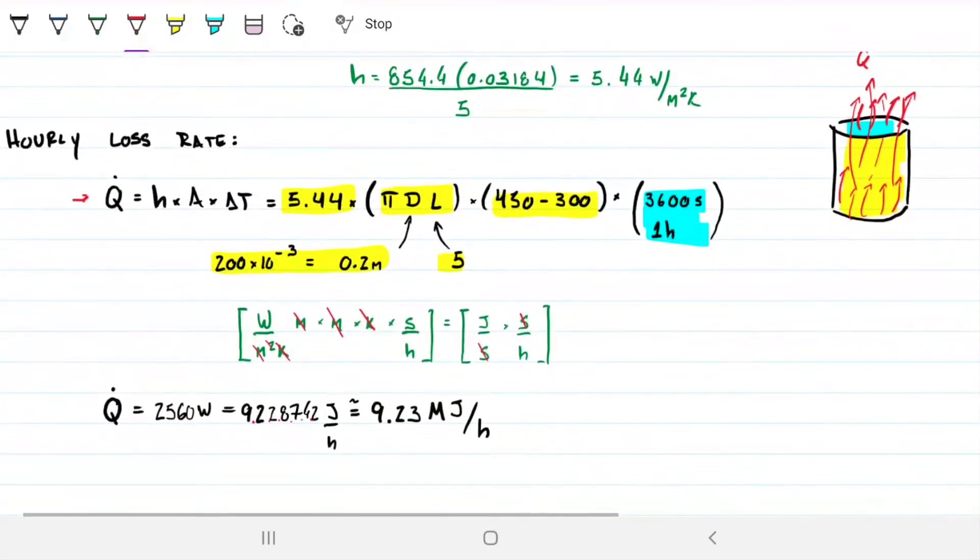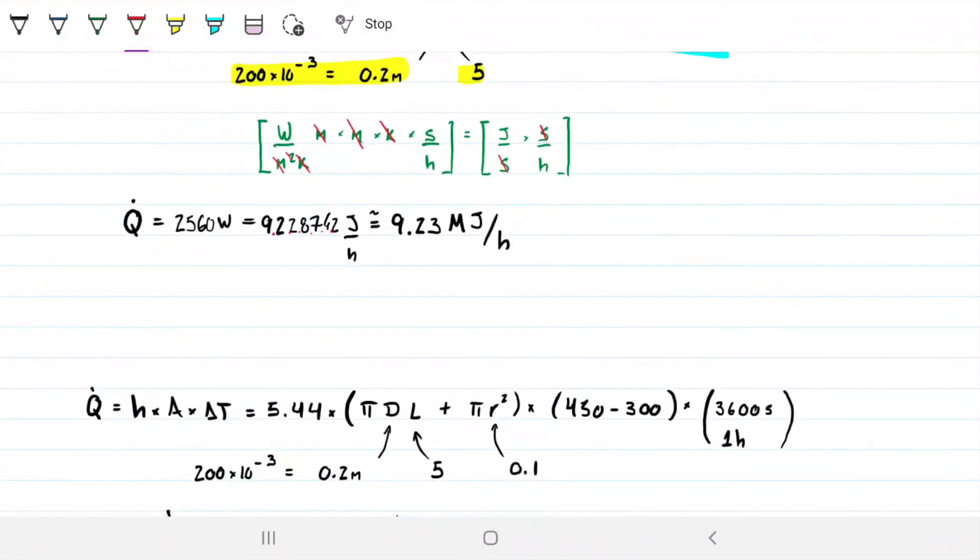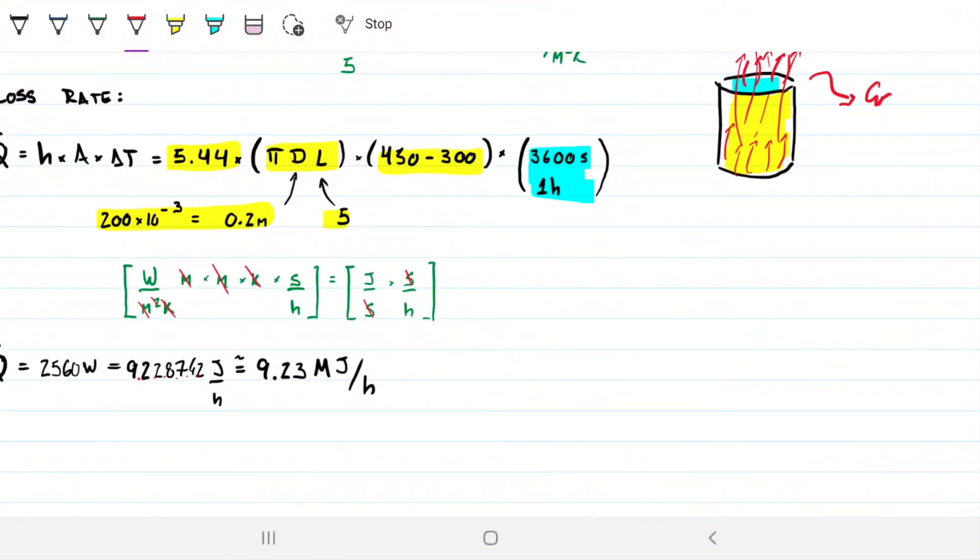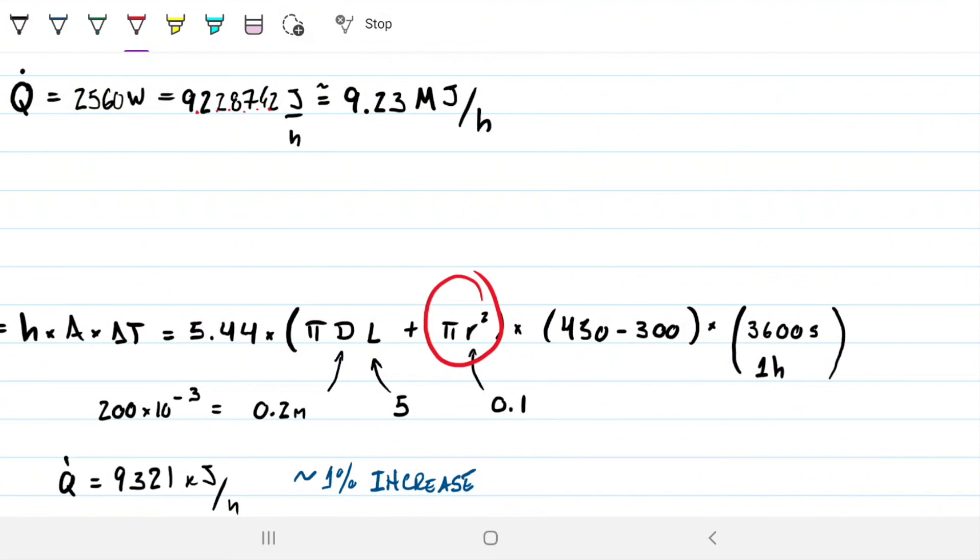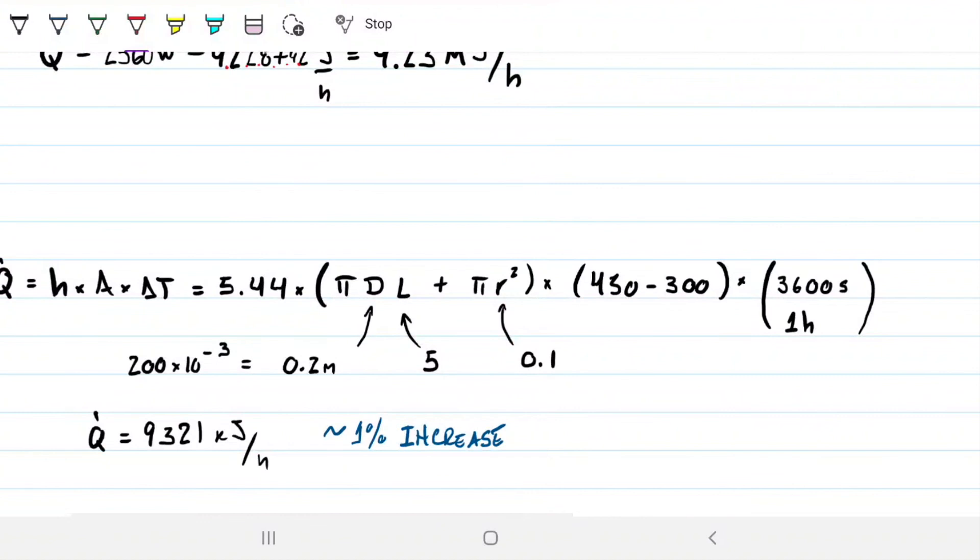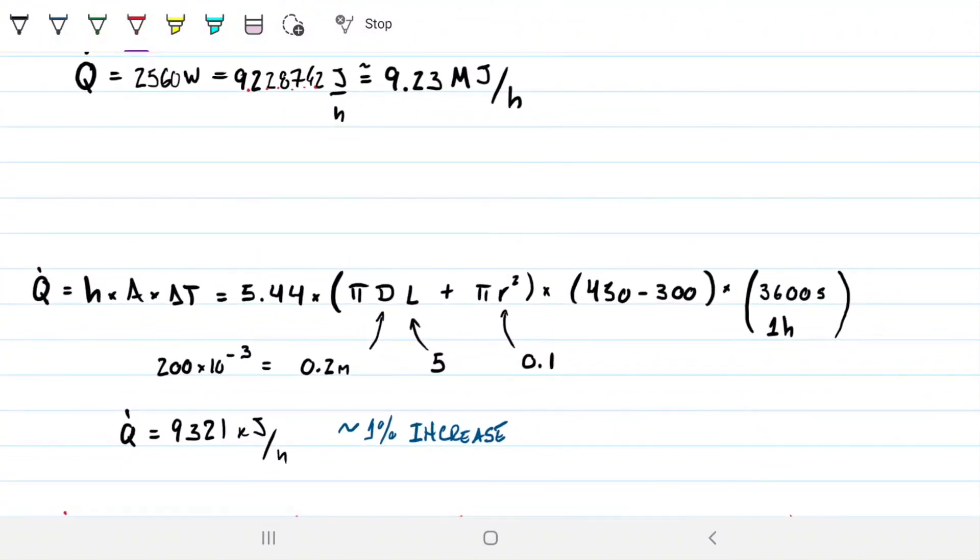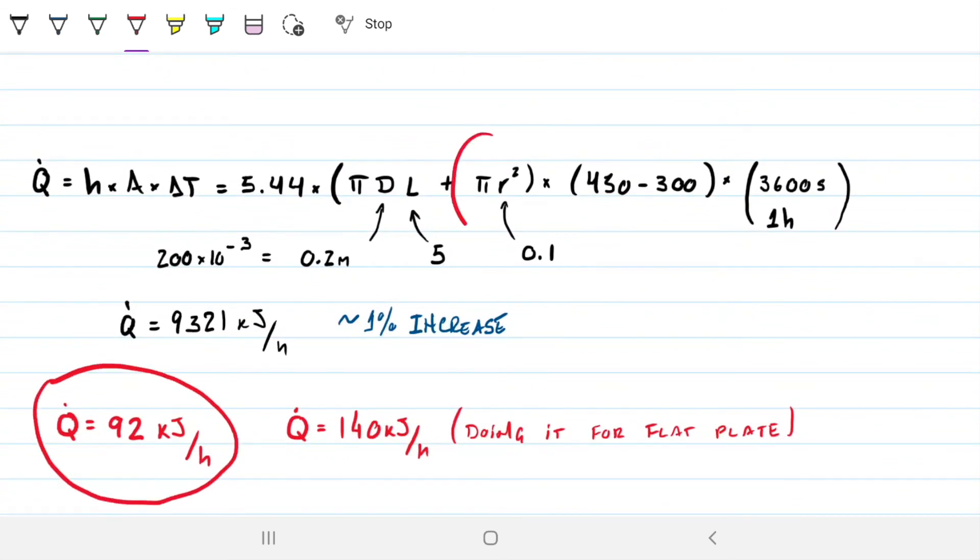So if you convert your watts into joules per second, and then you multiply by the relationship between seconds and hours, we remove these two seconds and we're left with joules per hour. So we'd have that in watts, and then if you convert it, you would have this big number in joules per hour, which we can say, instead of joules per hour, say megajoules per hour. So 9.23 approximately megajoules per hour is the hourly loss of heat of the cylinder under these conditions. Now, let's talk about the different areas, the different areas here, the blue and the yellow there. If I were to account for the blue area, what I need to do is actually do a flat plate analysis, because the top of the cylinder is a flat plate, a horizontal plate. So to do that, I'll need to calculate a different Grashof and et cetera, et cetera, et cetera. When we do this check here, it's precisely to see if we can neglect or ignore the top part.